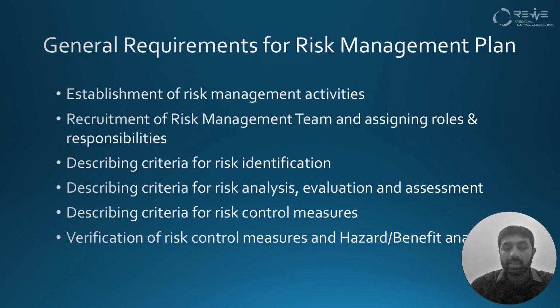After that, describing the criteria for risk control measures, like how we will plan our risk control measures and how we will implement them for controlling the impact of risk on our device or patient. And the last step is the verification of the risk control measures and the hazard benefit analysis of the risk control measure.